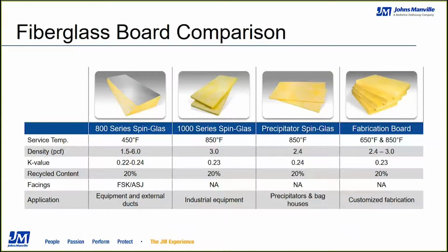The 800 series Spin-Glas, again, the core of the line, most frequently specified and utilized is the 814, which is a 3 pound per cubic foot density. It is typically used on the external outside of ducts as well as equipment, and often gets pinned and taped into place. 1000 series Spin-Glas is a 3 pound density, semi-rigid product, great for industrial applications with no facing.